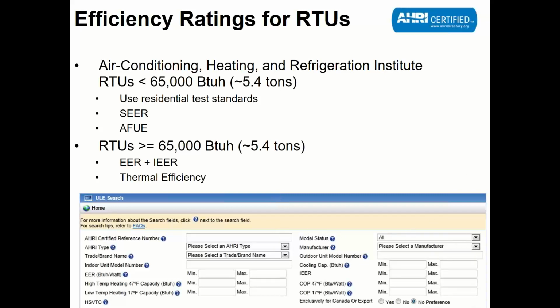Separate sidebar. Okay. For gas heating for rooftops, we use thermal efficiency. Thermal efficiency is kind of like the old school EER I was just explaining, but it's on the heating side. It means I'm going to run this system at maximum capacity, let everything settle out and equalize, and then measure how efficient it is. Whereas AFUE on the residential side takes into account part load. Commercially, we have no part load metrics on the heating side, on gas heating, only on the cooling side, and the cooling thing's relatively new.